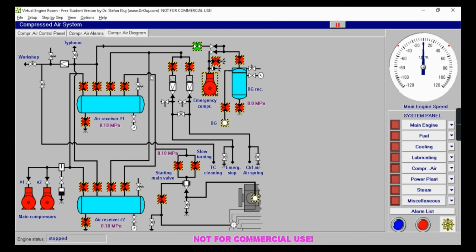Now, we will fill the diesel generator start air receiver. We will open its refilling valve and start the emergency compressor. We will wait until the air pressure is 2.5 megapascal or higher. Once it reaches 2.5 megapascal or higher, we will now stop the emergency compressor.